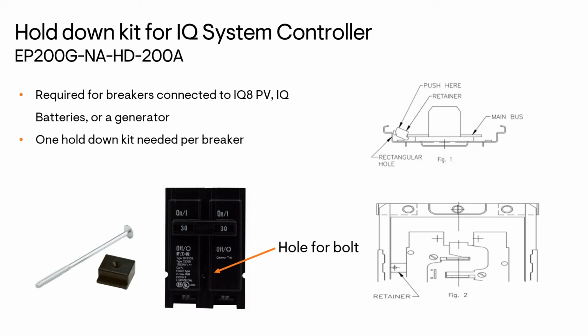To clarify, for solar only systems with IQ8, the system controller 2 is required, but the IQ combiner is optional. It's kind of the other way around. So when Enphase uses that term solar only, we're talking about a grid-tied system that doesn't provide backup power. So a solar-only configuration, therefore, does not require the system controller 2, because of course, you don't need to disconnect from the grid. And the use of a combiner isn't necessarily required either. Most installers use the combiner because the Envoy is built into it. It simplifies the installation, but it's not necessarily required for a solar-only configuration. It would be required for a sunlight backup configuration where it is providing backup power because you need those hold-down kits.